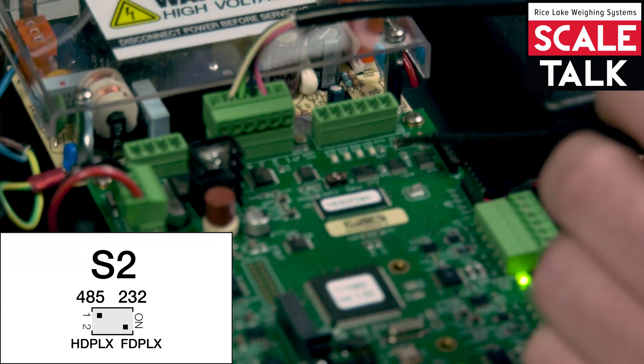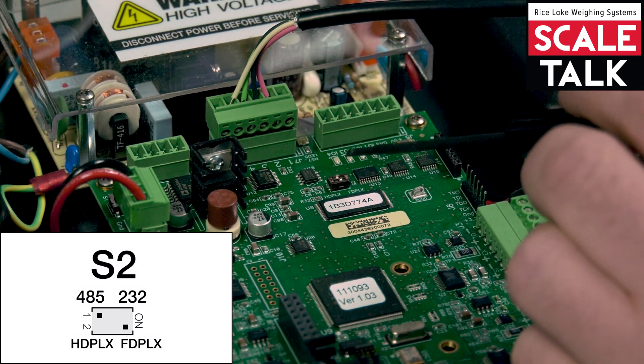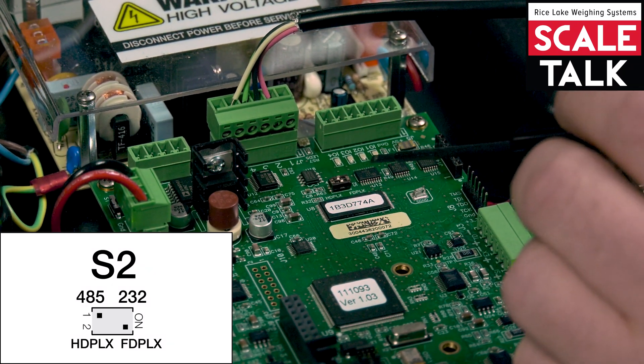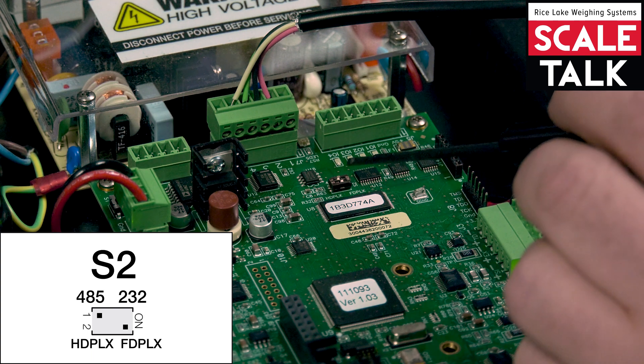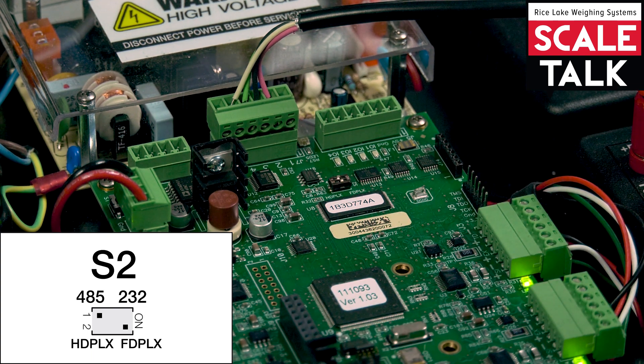Now for the 1280, you would want to use a four-wire — that's much better supported. If you were going to use a 920, you can use a two-wire, and you can switch the bottom switch over to the left-hand side for a two-wire 485 connection.